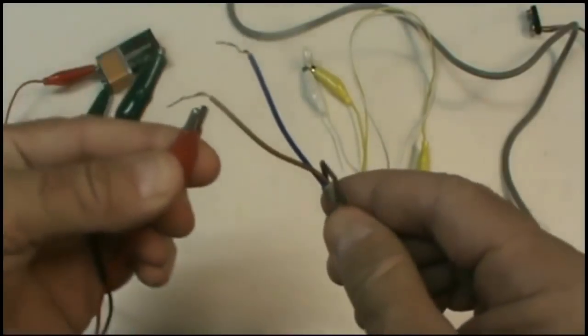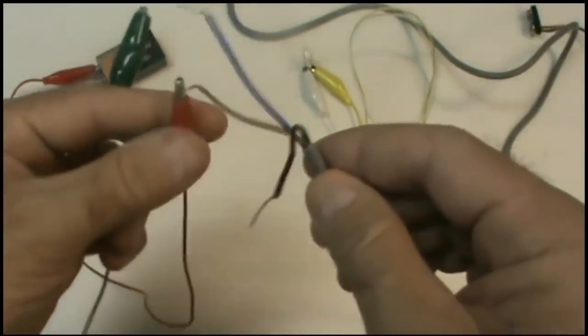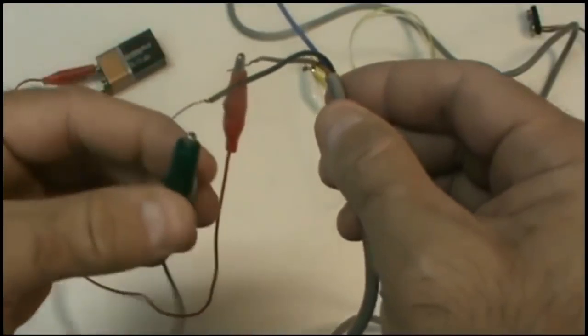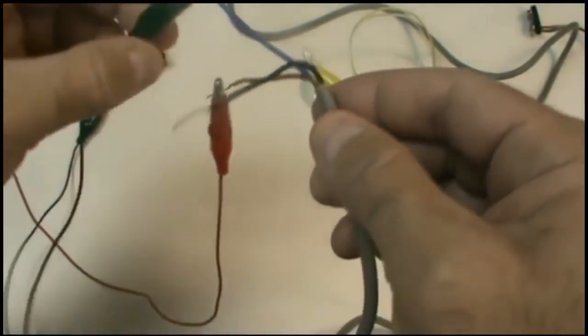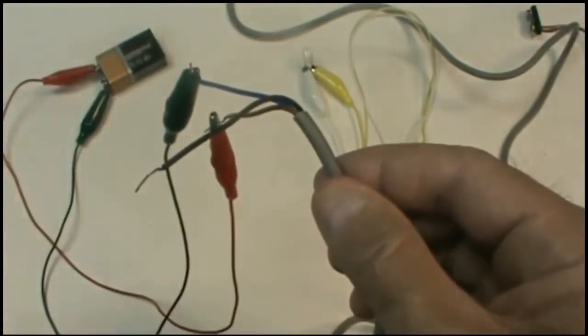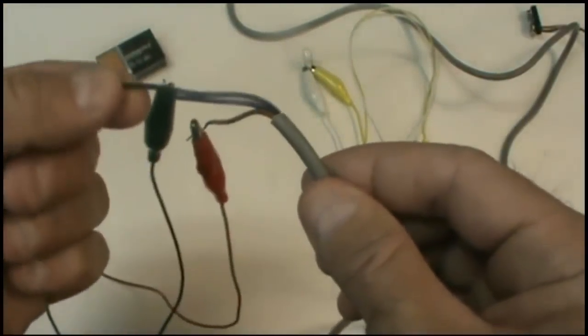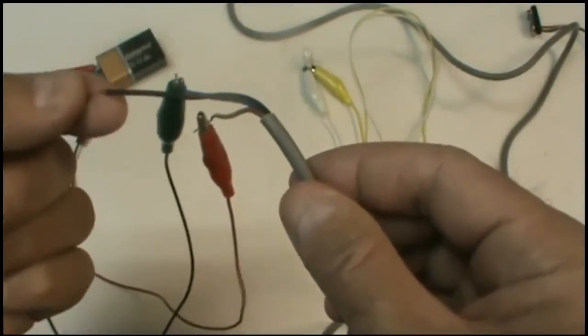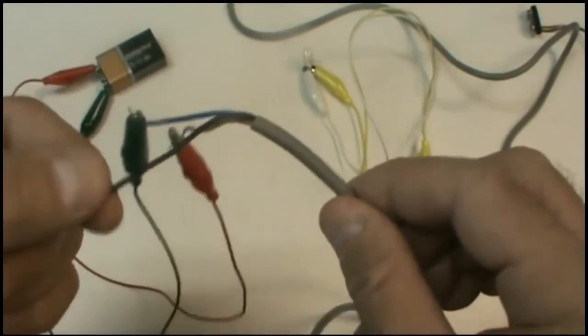So the red lead's going to go to my brown wire. The green lead is going to go to my blue wire. Don't go to black. That's easy to do because most of the time we identify black with negative, but that's not the case with sensors.